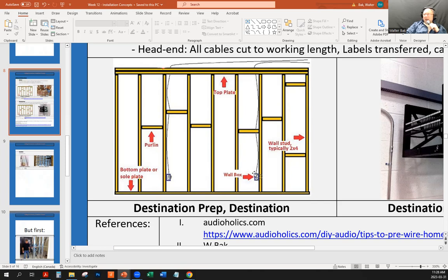Now, at the rough in stage, you can coil them here above, or sometimes you can run them to the box and coil them there. Now, which one do you do? You're going to have to decide. If there's a chance that there's going to be some other work being done here that is going to disturb your wires, then you're going to coil them here.